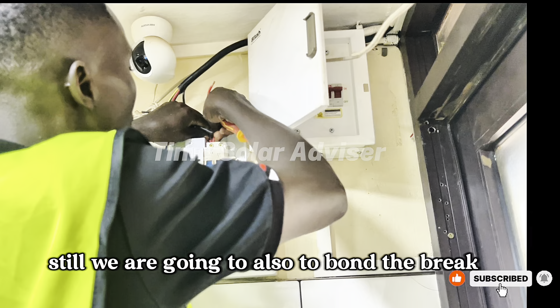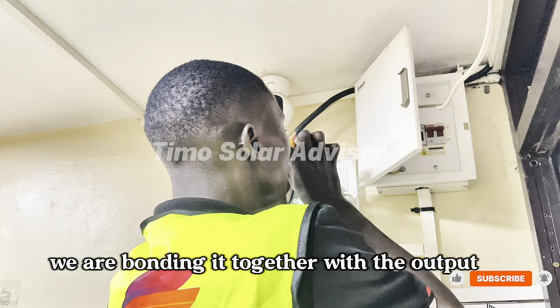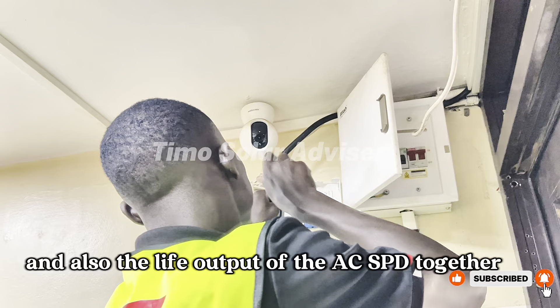Still, we are going to also bond the SPD together with this output, which is going to the inverter. So right now we have connected the output from the mains, which is going to the inverter input. So still I have to bond the SPD together with the output power, which is going to the inverter, so that it can remove any surge which is going directly to the inverter. We are bonding it together with the output going to the inverter, and also the live output of the SPD together. So right now we also are going to bond the neutral. So this is the neutral which is going to the inverter. You have to bond it together with the neutral of the SPD.